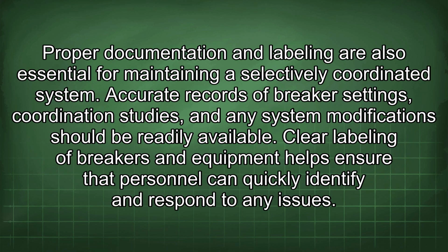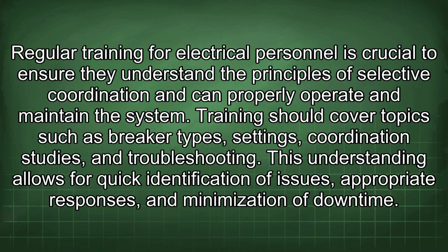Proper documentation and labeling are also essential for maintaining a selectively coordinated system. Accurate records of breaker settings, coordination studies, and any system modifications should be readily available. Clear labeling of breakers and equipment helps ensure that personnel can quickly identify and respond to any issues. Regular training for electrical personnel is crucial to ensure they understand the principles of selective coordination and can properly operate and maintain the system. Training should cover topics such as breaker types, settings, coordination studies, and troubleshooting. This understanding allows for quick identification of issues, appropriate responses, and minimization of downtime.